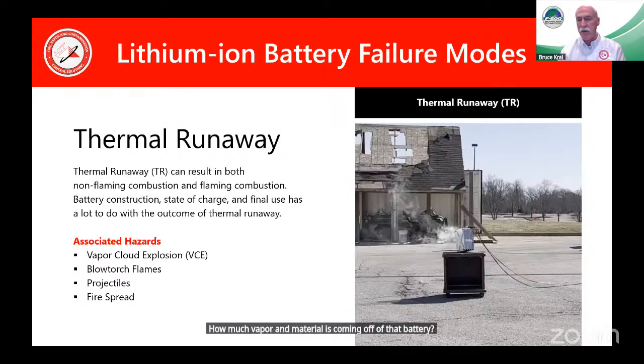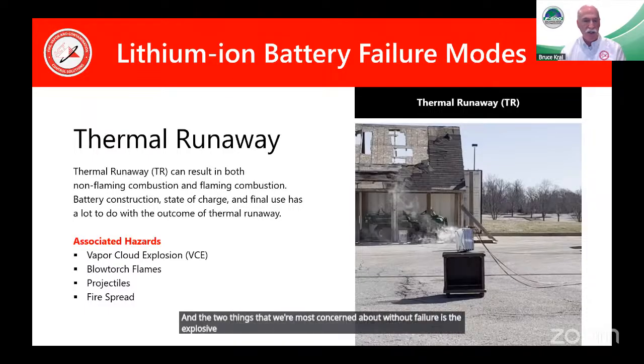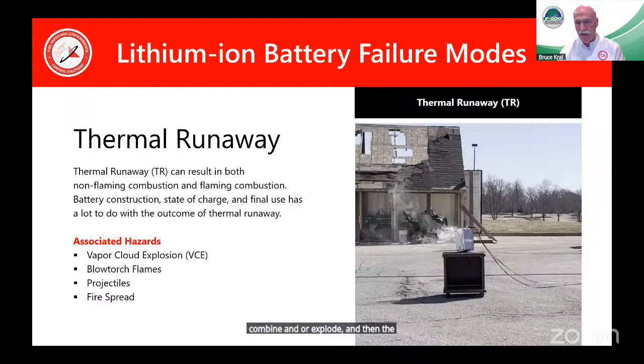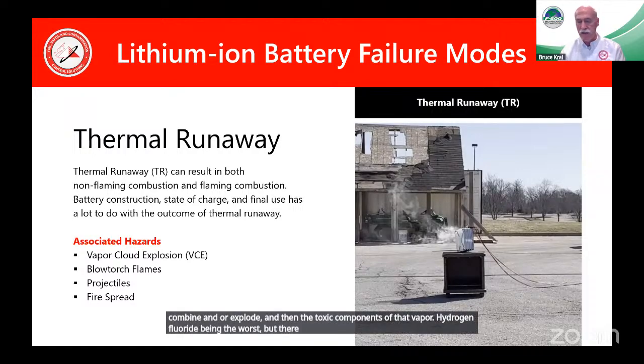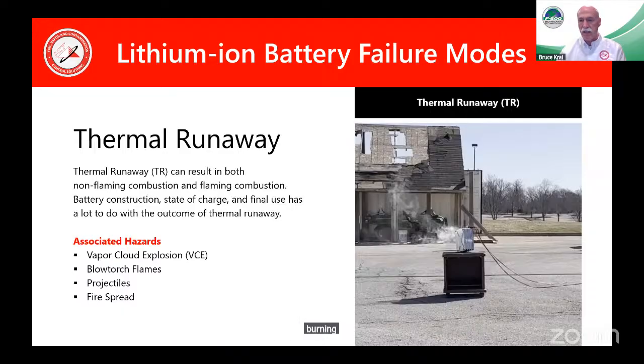The two things we're most concerned about with that failure are the explosive vapors - the hydrogen ions that are ready to combine and/or explode - and then the toxic components of that vapor, hydrogen fluoride being the worst, but there's many more in there. So that failure, even though it's not burning, you're building up vapors to an explosive level, or you're creating toxins in a high volume.